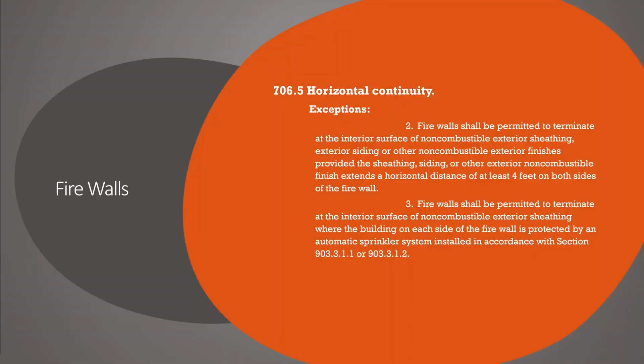Exception number 3, firewall shall be permitted to terminate at the interior surface of a non-combustible exterior sheathing where the building on each side of the firewall is protected by an automatic sprinkler system installed in accordance with 903.3.1.1 or 903.3.1.2. So yep, there's sprinkler forgiveness there for complying with NFPA 13. And note that it says the building. So not just a portion of the building on either side, but both buildings on either side of the firewall, and the whole building is sprinklered as required.